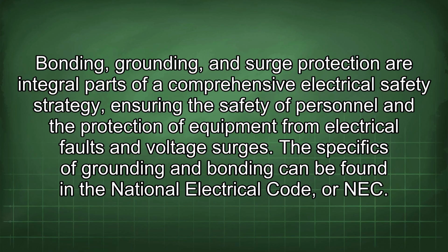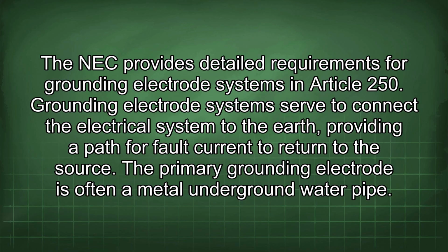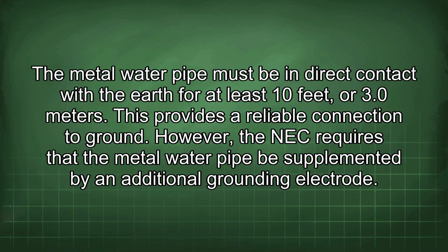The specifics of grounding and bonding can be found in the National Electrical Code, or NEC. The NEC provides detailed requirements for grounding electrode systems in Article 250. Grounding electrode systems serve to connect the electrical system to the earth, providing a path for fault current to return to the source. The primary grounding electrode is often a metal underground water pipe. The metal water pipe must be in direct contact with the earth for at least 10 feet or 3.0 meters. This provides a reliable connection to ground.